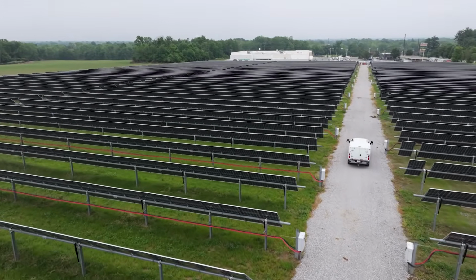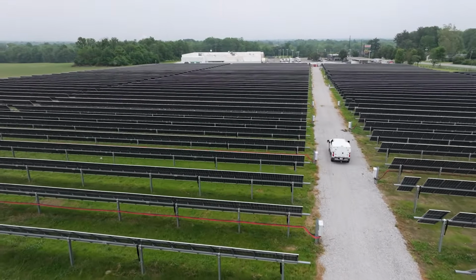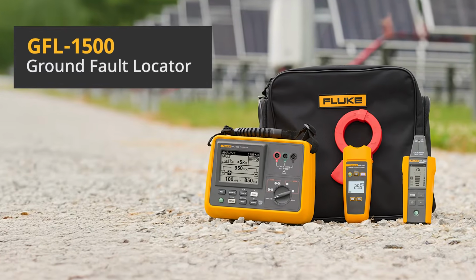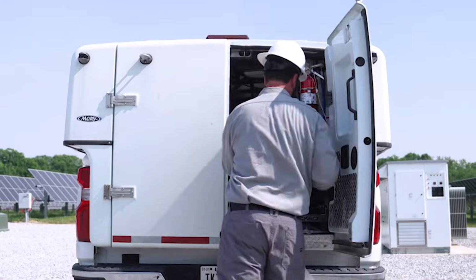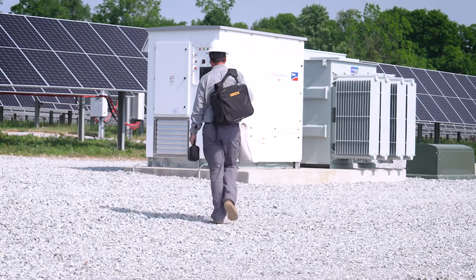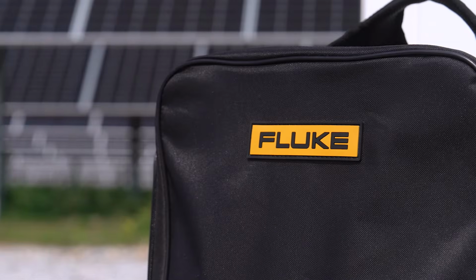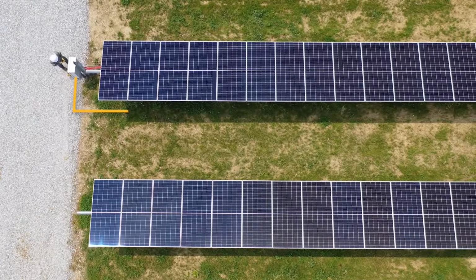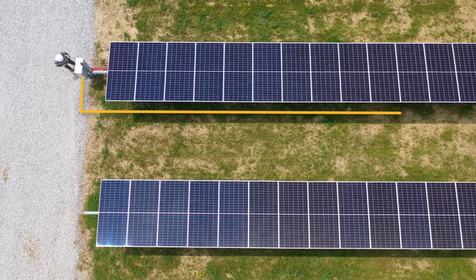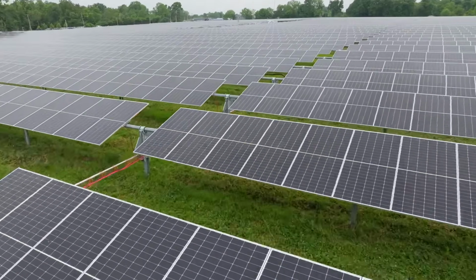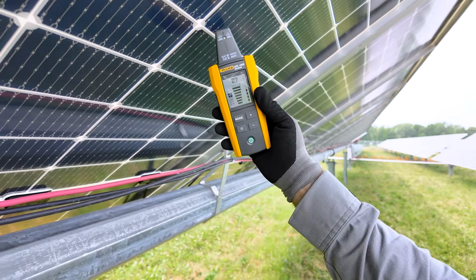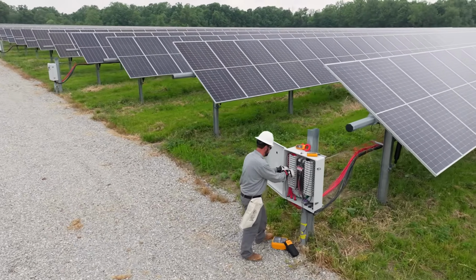Still wasting hours searching up and down for a ground fault? Not anymore. With the GFL-1500 ground fault locator, what used to take hours now takes minutes. This three-piece troubleshooting system uses fault track technology to generate a traceable signal through the fault path. This innovative solution redefines how technicians locate active ground faults in solar PV systems.